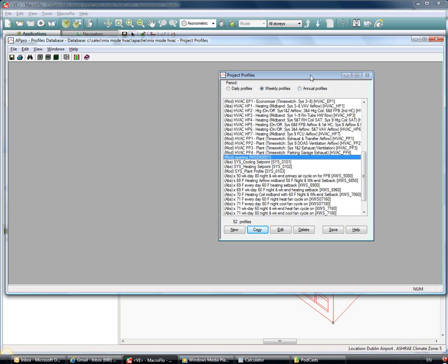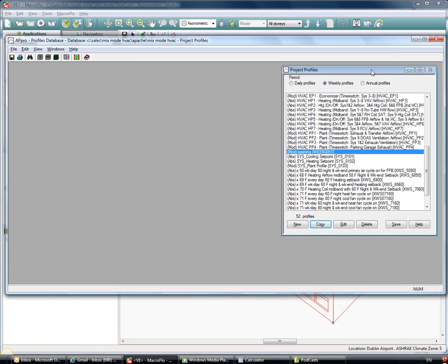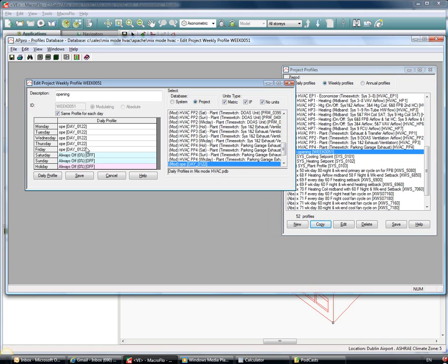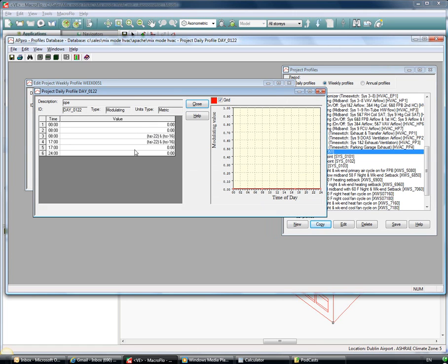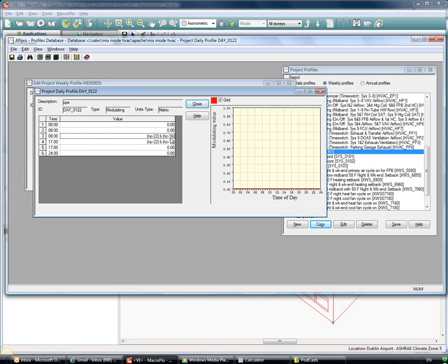The opening profile is a formula profile. So as I've opened my profile database I can see here that we have our opening weekly profile. And as I look at the daily profile associated, I can see it's a formula profile which between the hours of 8 and 5 is allowing the windows to be openable when the air temperature in the room goes above 22 degrees and when the outside air temperature is greater than 16.